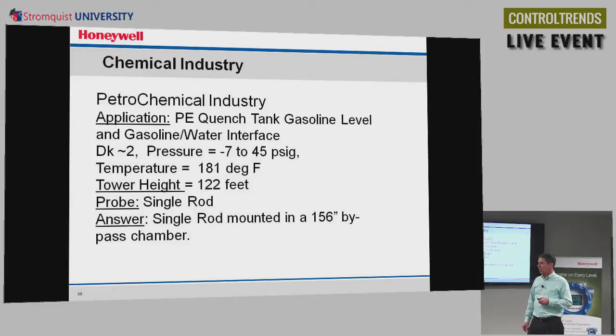And here's a look at a specific application. This is in an ethylene plant on a quench tank. In this application, there's a combination of gasoline and water in a tank, and they want to measure the surface and they want to measure the interface, and they're going to use a bypass. And guided wave works real well in the bypass. It's going to measure the level at the top. So it's gasoline and water. Gasoline is going to be floating on the top, water's on the bottom, so they're measuring that level. Then they measure the interface between the gasoline and the water, and they're able to control based off of that. Again, done in a bypass. And this will be a single rod mount.